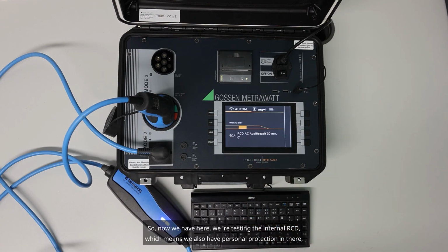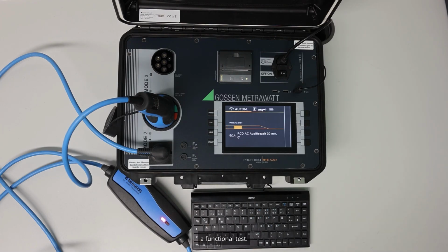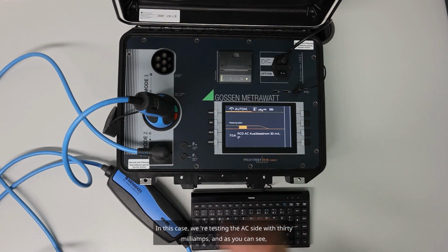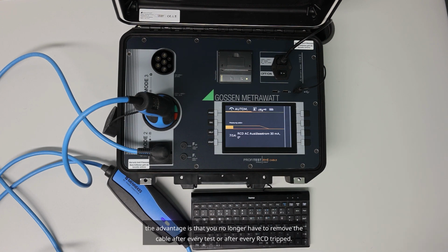So now we have here, we're testing the internal RCD, which means we also have personal protection in there, a functional test. In this case, we're testing the AC side with 30 milliamps, and as you can see, the advantage is that you no longer have to remove the cable after every test or after every RCD tripped. That means if you test the whole thing manually, it's quite possible, depending on the cable, that you'd have to disconnect the input side, meaning the main side, or even the vehicle side. And only then you can put the cable back into operation and restart the measurement. That's not the case here. It's done automatically. You can see it clearly.